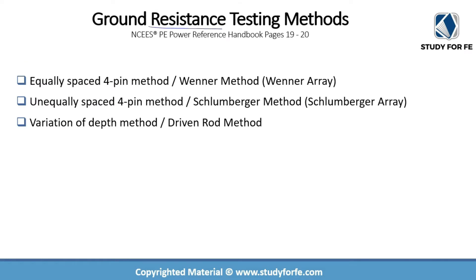There are many different methods for ground resistance testing. When you go through those IEEE standards you will find additional methods beyond the three discussed in the NCEES PE Power Reference Handbook. Each method has its own advantages and disadvantages — some are simpler to conduct, some provide higher accuracy at the expense of a more sophisticated setup. For our purpose we will look at the Wenner method with equally spaced four pins, the Schlumberger method with unequally spaced four pins, and the driven rod method using one test electrode.